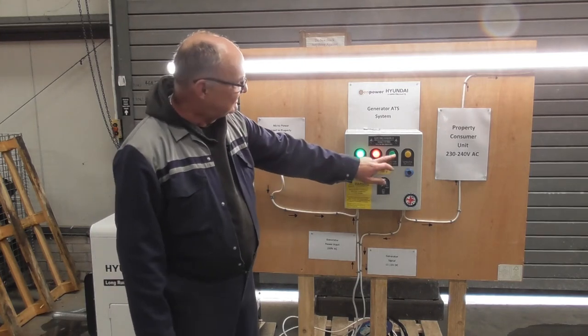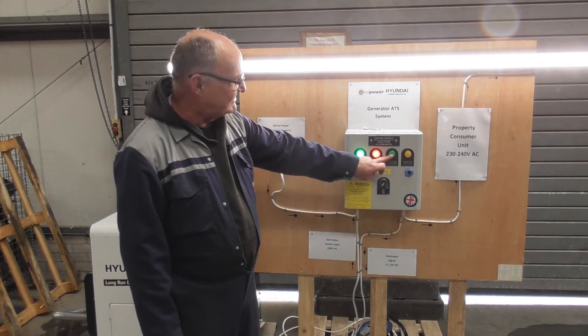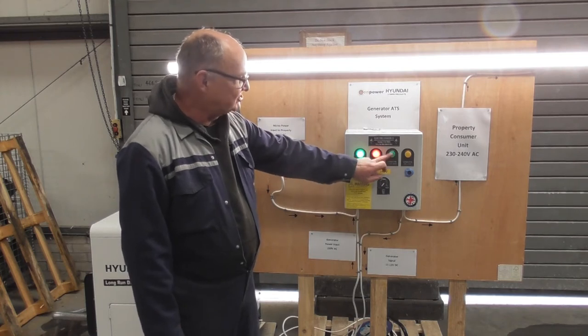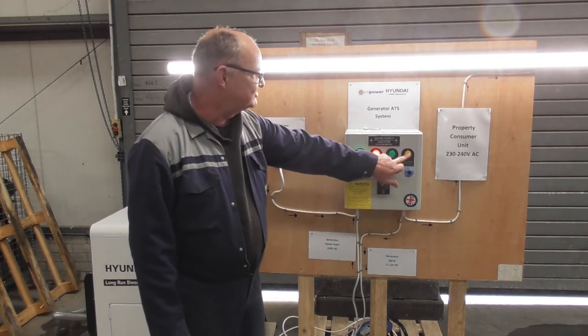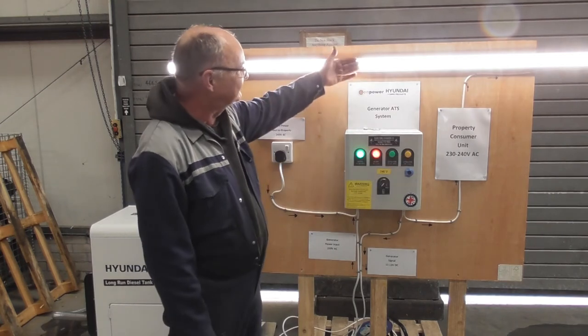Once the generator's started we'll see this green light come on to say the generator's available and then after a short delay period which is built into the unit and can be adjusted, the generator will then take the load and you'll see the light come back on.